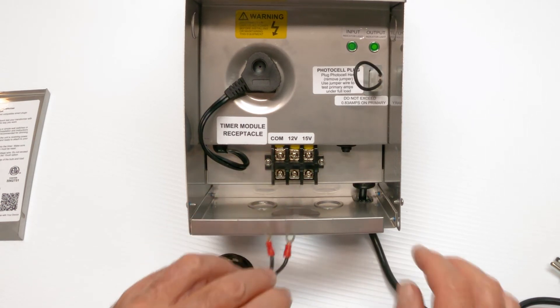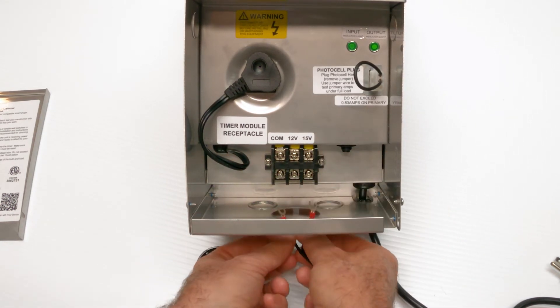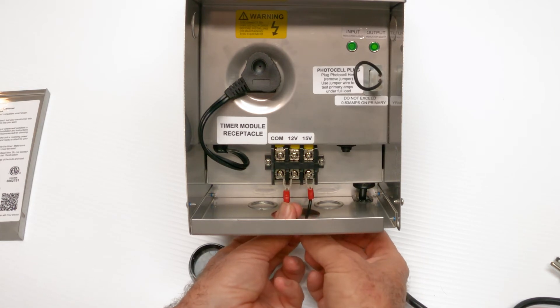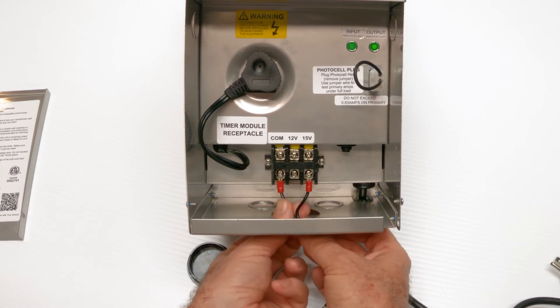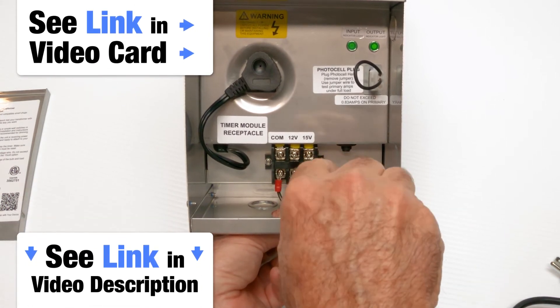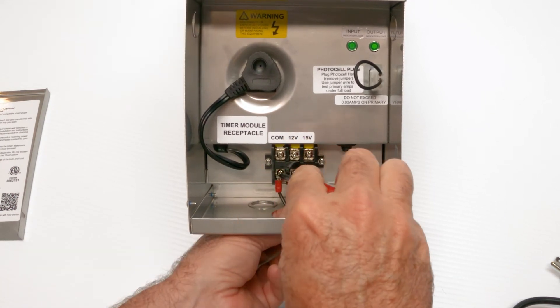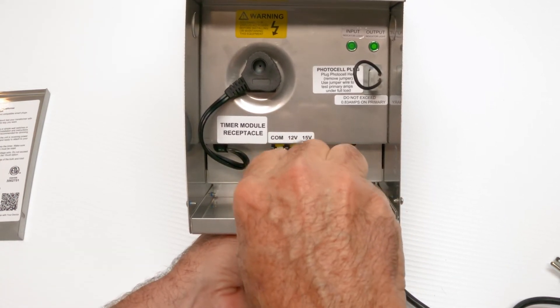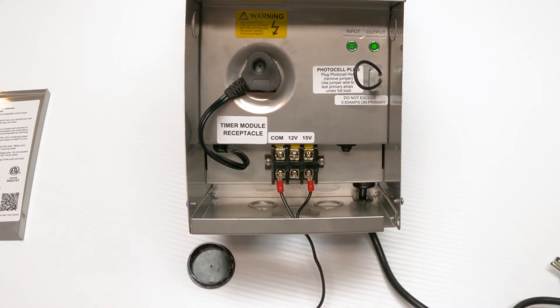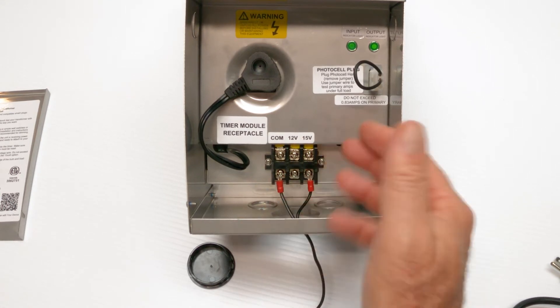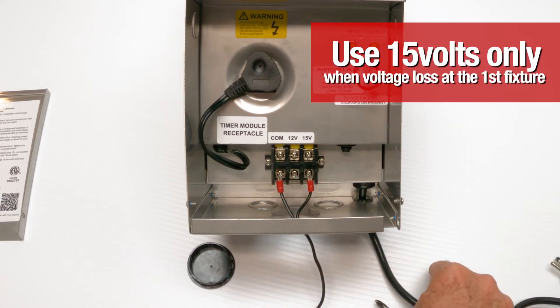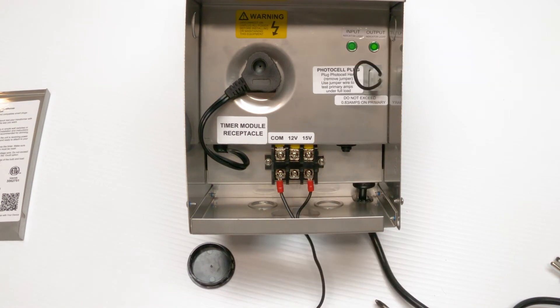Now there is a 15 volt option here where you would run it this way. If you're running really long loads out there in the field and you need a little extra voltage boost. Now we have a video on landscape lighting voltage loss where we did a real field test and we addressed this 15 volt. I don't want you to connect to it right away.